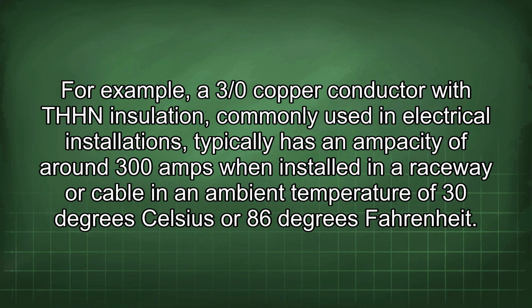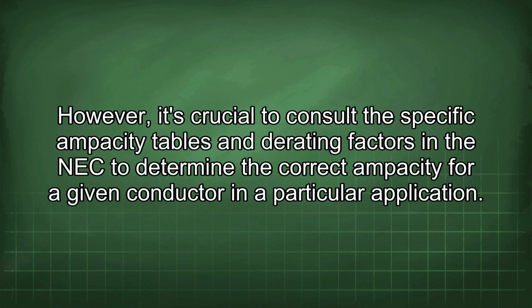For example, a 3/0 copper conductor with THHN insulation, commonly used in electrical installations, typically has an ampacity of around 300 amps when installed in a raceway or cable in an ambient temperature of 30 degrees Celsius or 86 degrees Fahrenheit. However, it's crucial to consult the specific ampacity tables and derating factors in the NEC to determine the correct ampacity for a given conductor in a particular application.